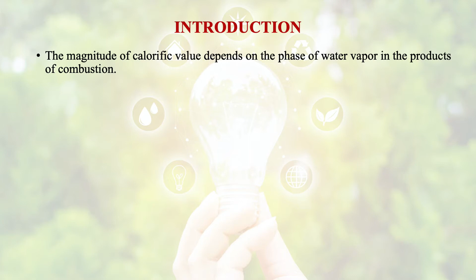So we have two kinds of heating value. One is higher heating value or gross calorific value. Higher heating value or gross calorific value is obtained when the water formed by combustion is completely condensed. The second one is lower calorific value or net calorific value, and it is the amount of heat released by complete combustion of unit quantity of fuel when vapor carries its heat of vaporization.